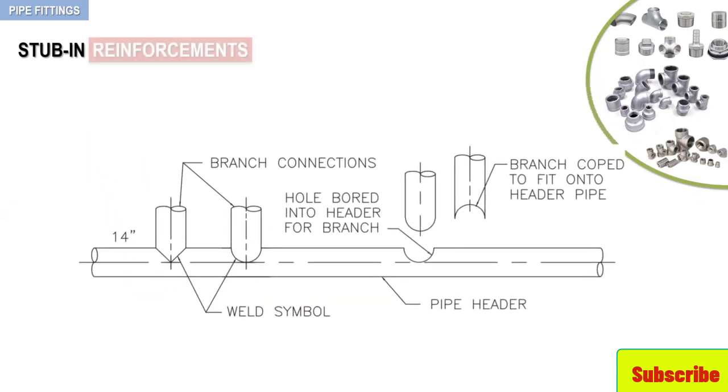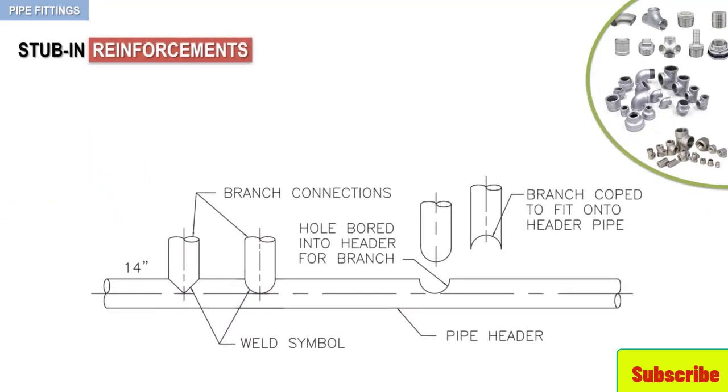When internal conditions such as pressure or temperature of the fluid, or external forces such as vibrations or pulsations are placed on a stub-in, special reinforcement may be necessary to prevent the branch from separating from the header. In this video, three reinforcing alternatives will be discussed: reinforcing pad, welding saddle, and O-lets.